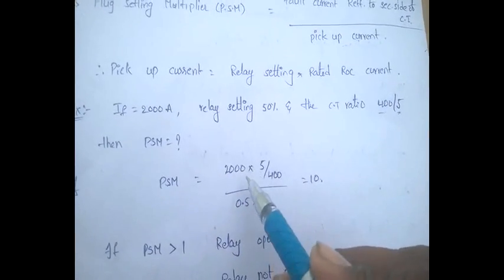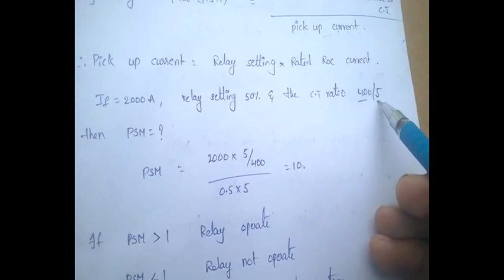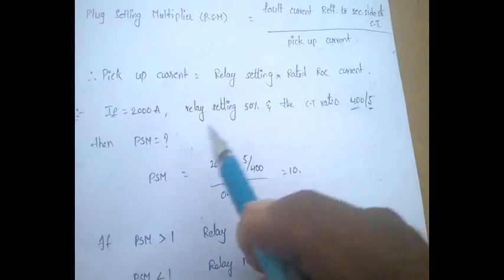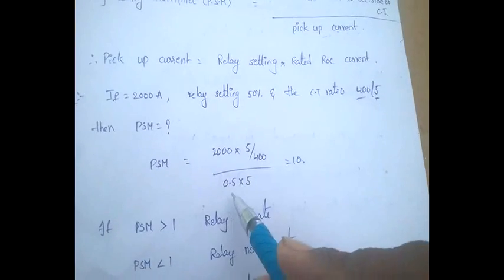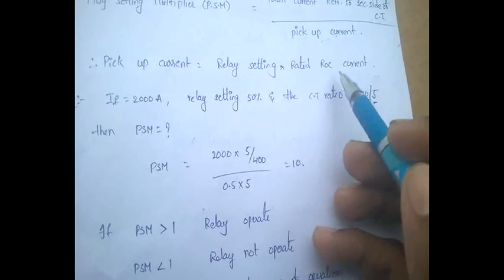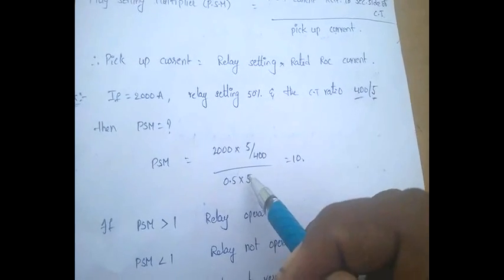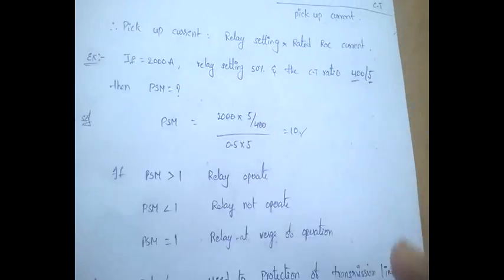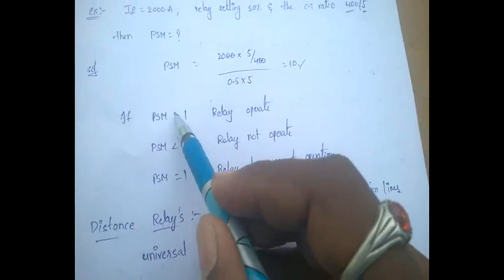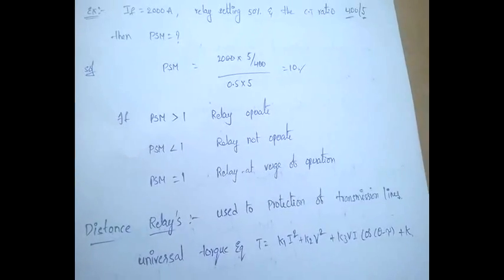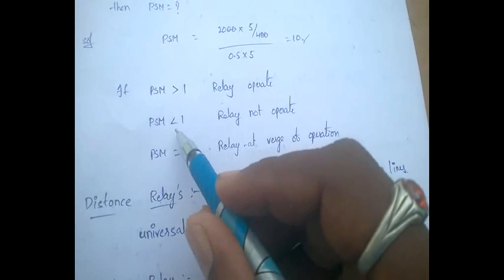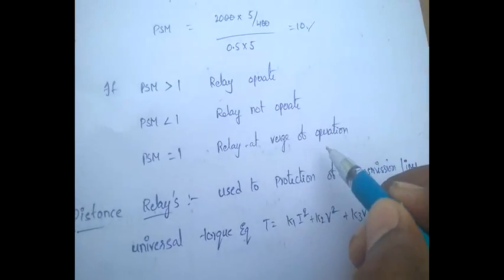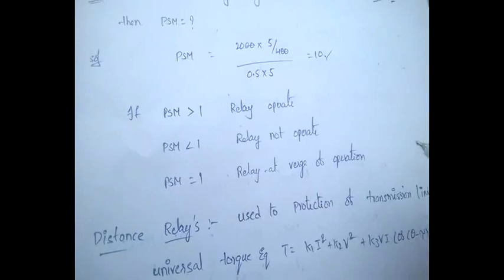To find PSM: fault current referred to secondary = 2000 × (5/400). Pickup current = 0.5 × 5. Simplifying gives PSM = 10. If PSM is greater than 1, the relay will operate. If PSM is less than 1, the relay will not operate. If PSM equals 1, the relay is at the verge of operation — it is in dilemma whether to operate or not.